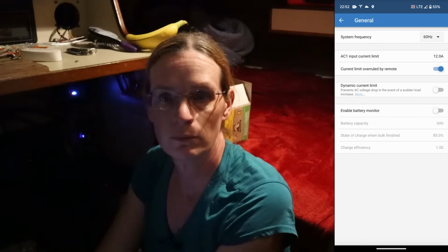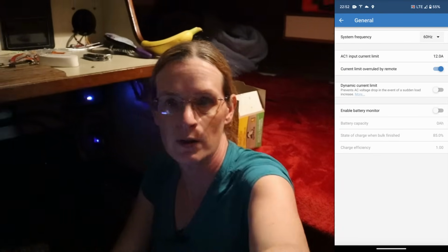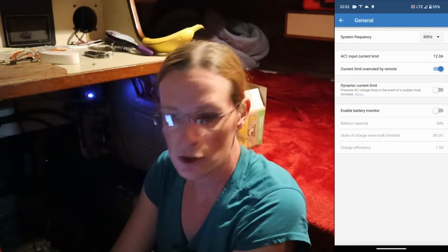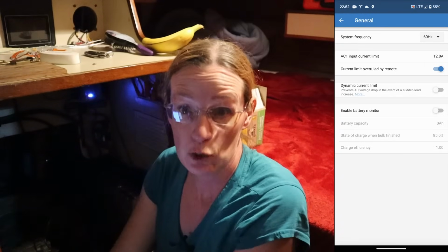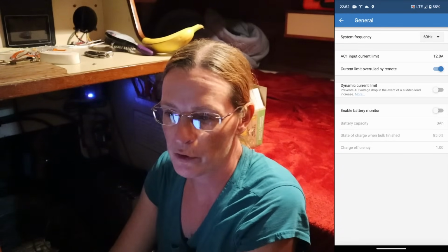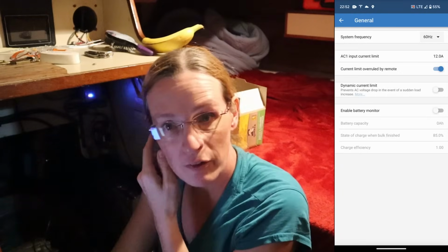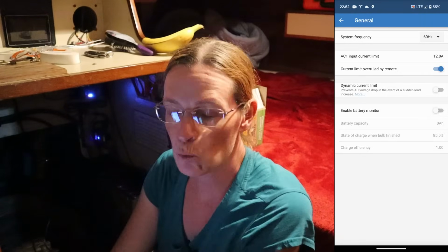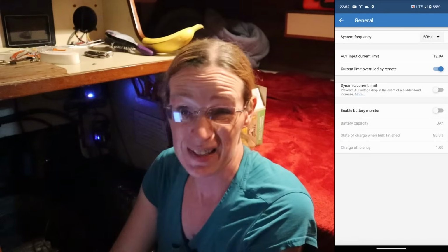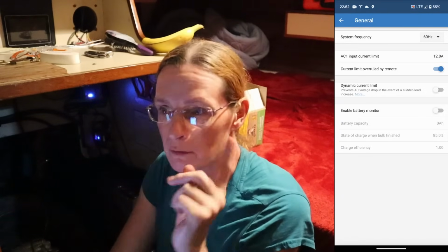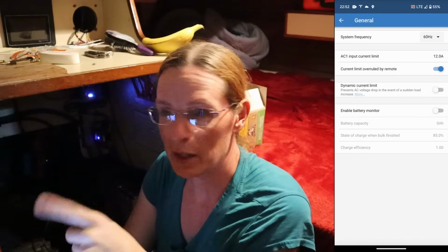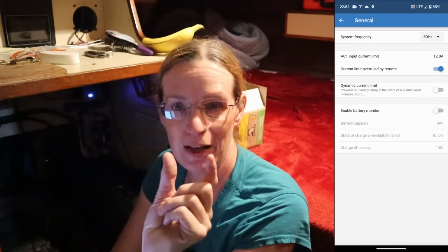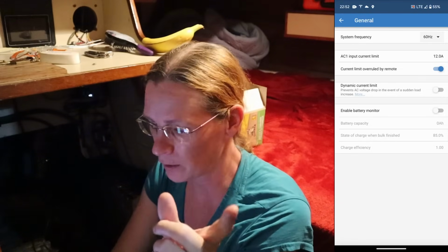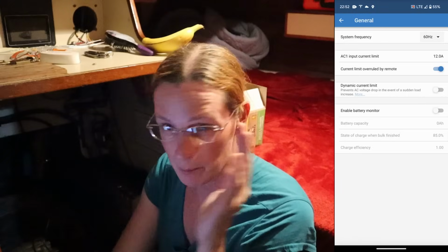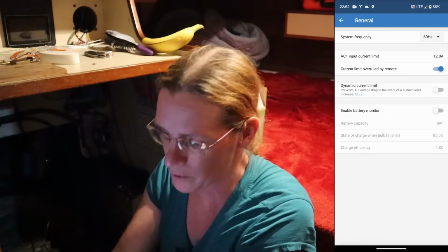Current limit is still 12 amps. I went on to Southwire's voltage drop calculator, and at 12 amps, the voltage drop over the 50 feet of 12 gauge wire is 1.75%. Just in case anybody's worried about me running the extension cord to the 15 amp NEMA 5-15 plug, even though it's a 20 amp wire, I'm staying well below what the wire is capable of carrying.